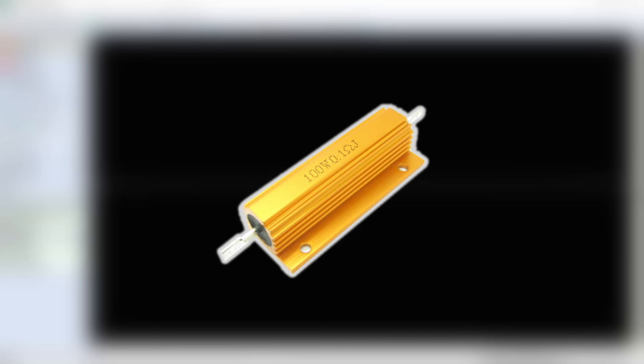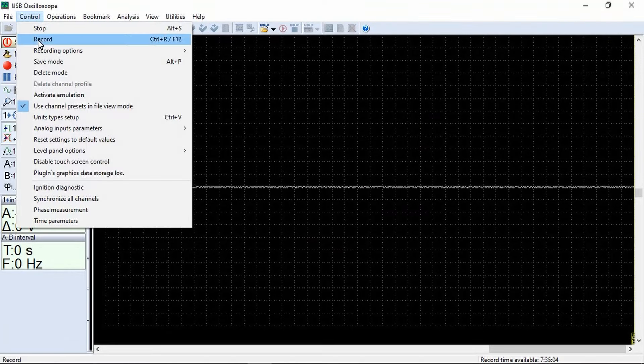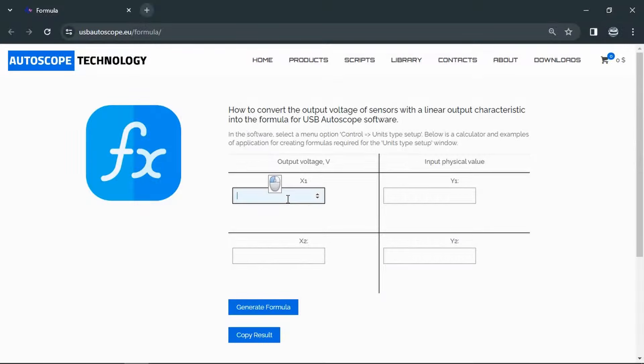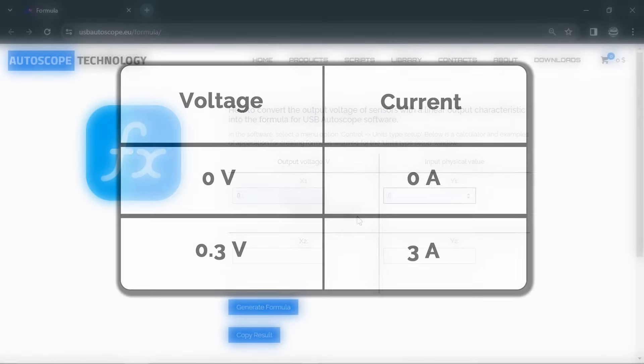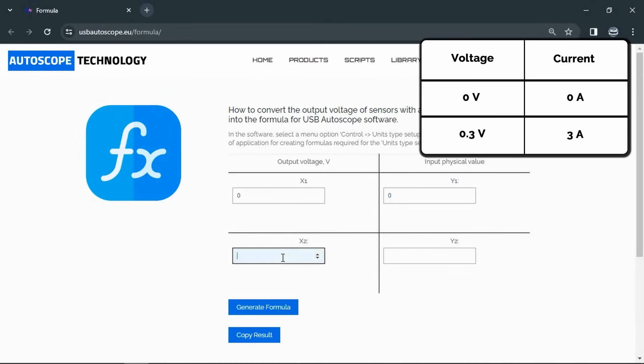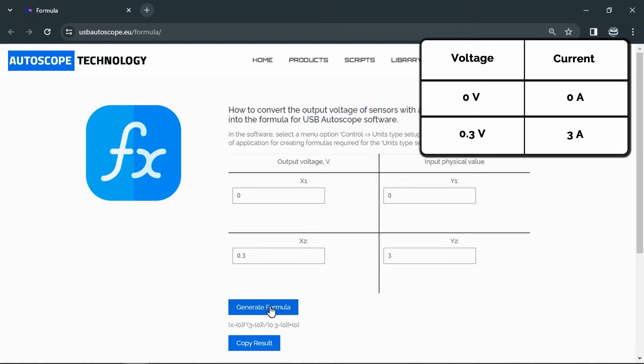Next example: a resistor with a resistance of 0.1 ohm, which we will use as a shunt for measuring current. We add a new transducer, name it 'shunt', and set the unit of measurement to amperes. We create a formula for the shunt. The first two values are 0 volts corresponding to 0 amperes. According to Ohm's law, a voltage of 0.3 volts is required to drive a current of 3 amperes through a resistance of 0.1 ohm. We enter the next two values: 0.3 volts and 3 amperes. We generate the formula and copy it into the program.